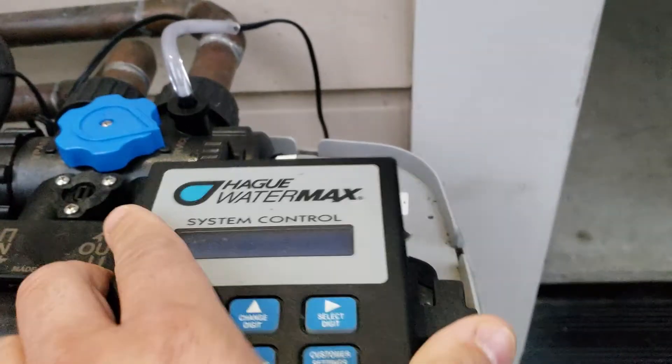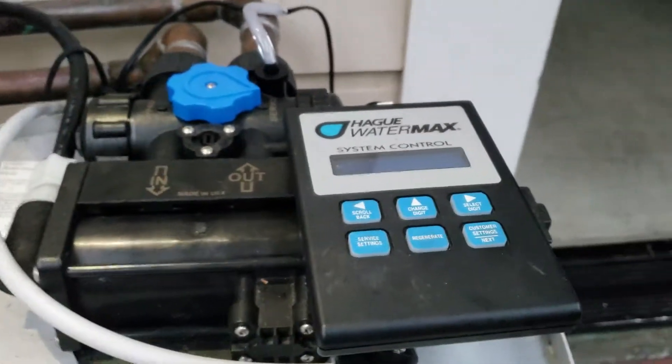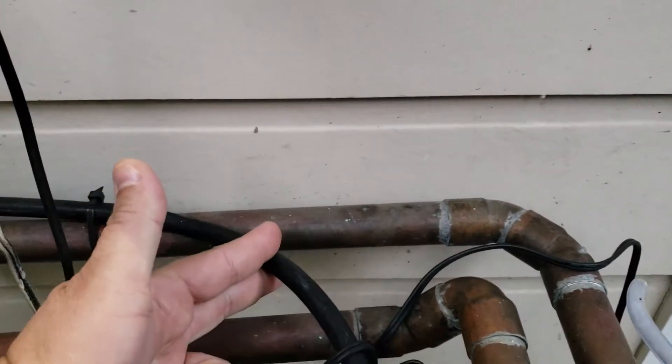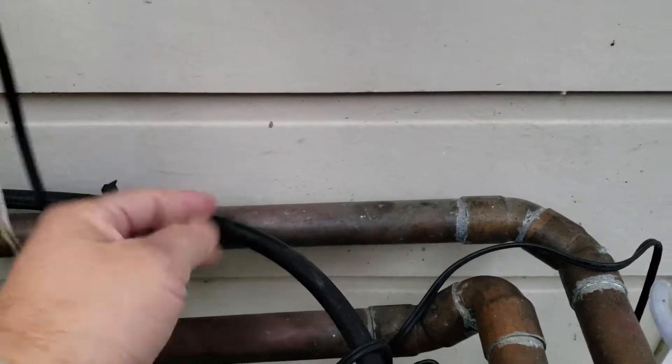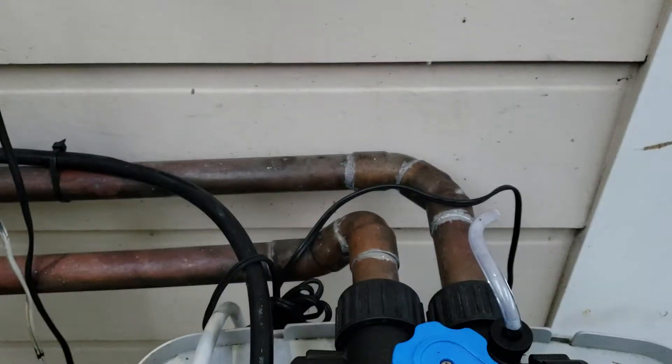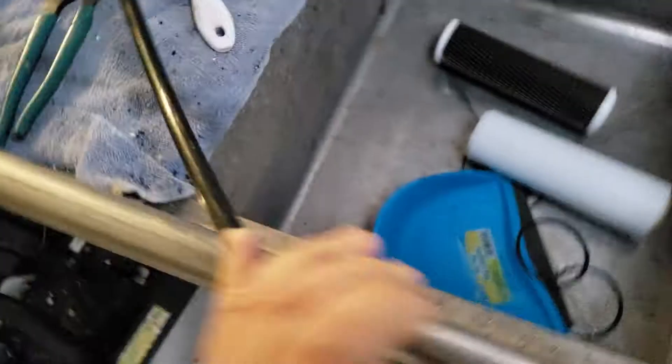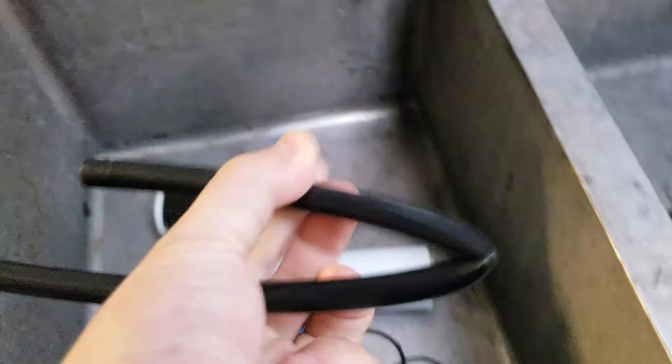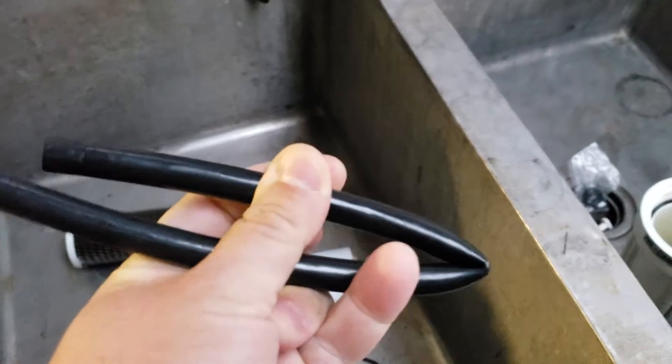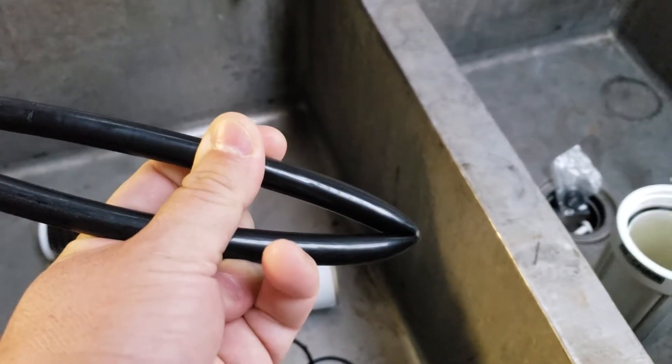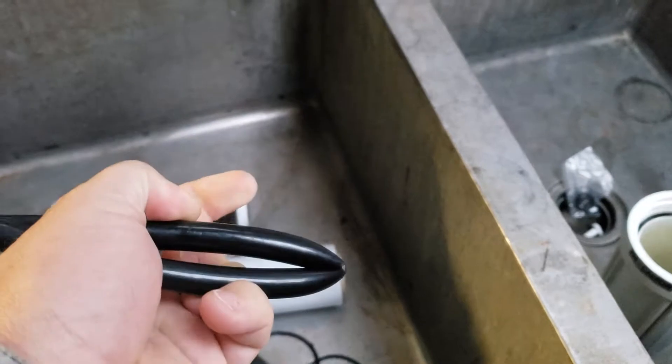And if that still doesn't work, the last resort would be to cut the drain line with some scissors and then fold the drain line over itself, something like this. So you cut the end of it and then fold the drain line in half to the point where it kinks. Put a zip tie around it or piece of tape. That will at least keep the water from running down to the drain and buy us time to come out and do a service call to resolve the issue.